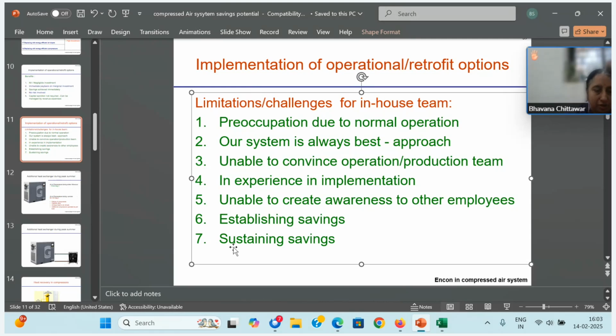And now his next question is, will loading and unloading occur in a VFD operated screw compressor? And is there any specific reason for that? Yeah, correct. See, sometimes VFD compressors would have locked the speed, minimum and maximum speed. So the speed reduces to the lowest set point.